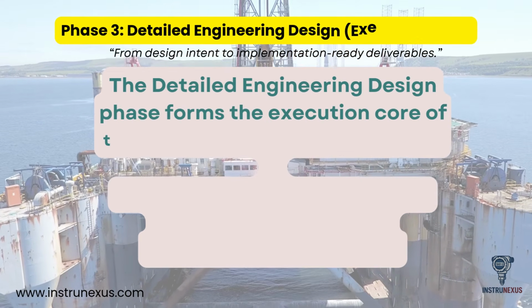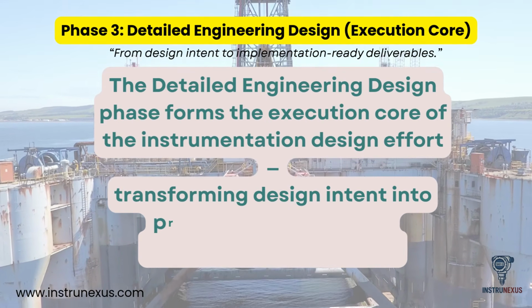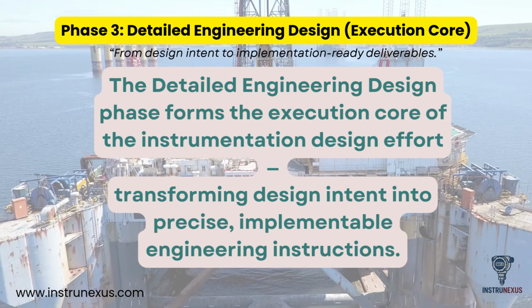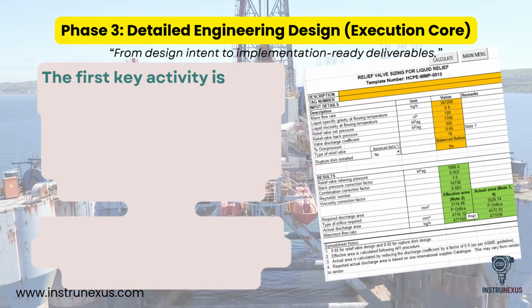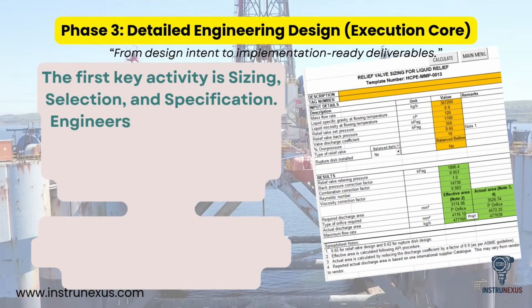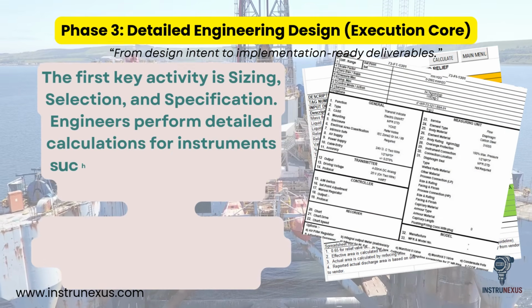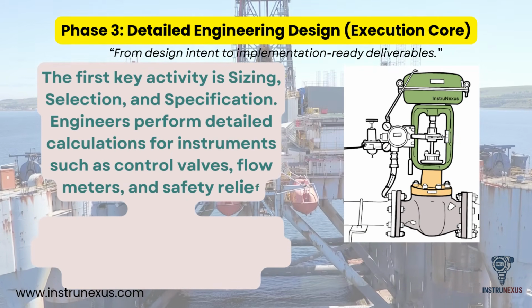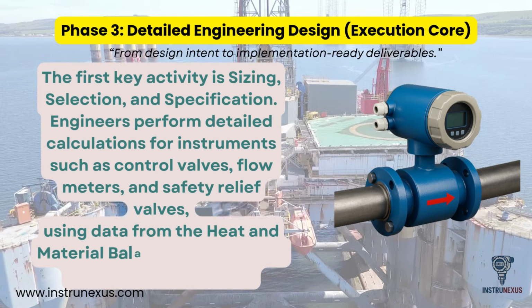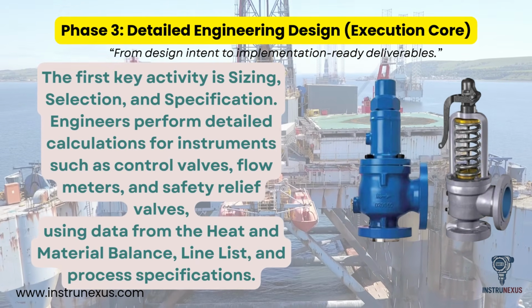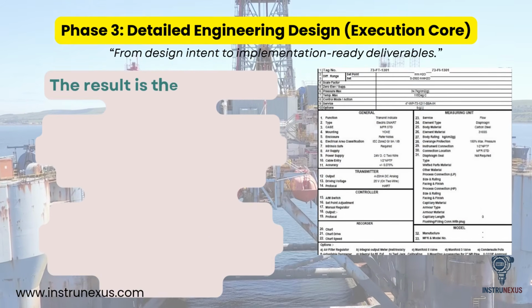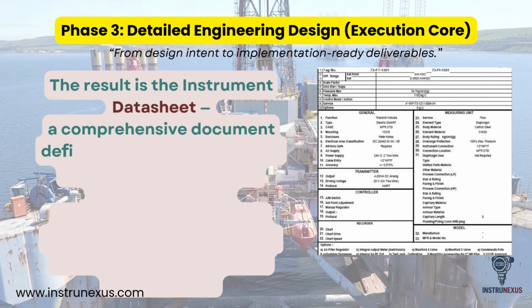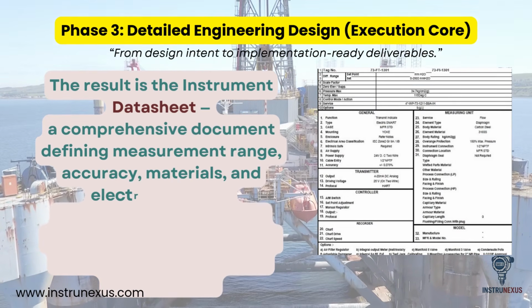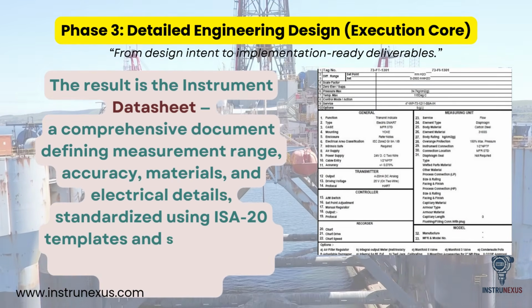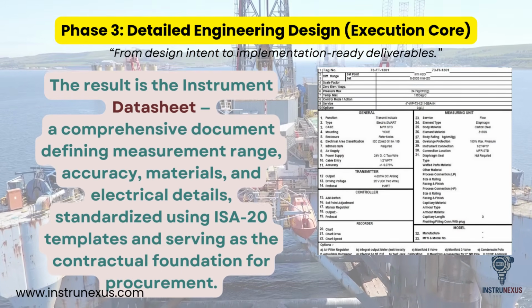The detailed engineering design phase forms the execution core of the instrumentation design effort, transforming design intent into precise, implementable engineering instructions. The first key activity is sizing, selection, and specification. Engineers perform detailed calculations for instruments such as control valves, flow meters, and safety relief valves using data from the heat and material balance, line list, and process specifications. The result is the instrument datasheet, a comprehensive document defining measurement range, accuracy, materials, and electrical details, standardized using ISA 20 templates and serving as the contractual foundation for procurement.